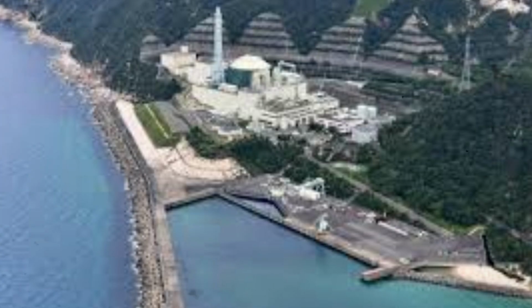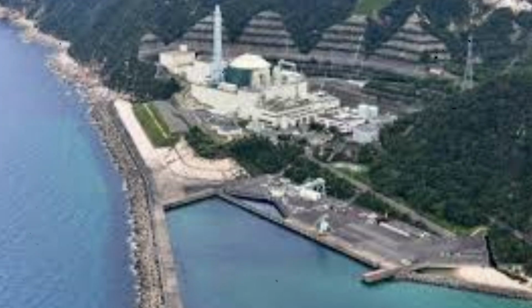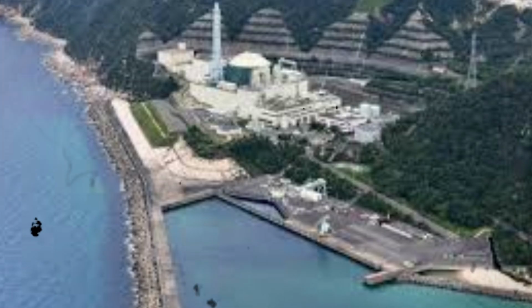However, initial notifications were based on preliminary assessments of leak severity that proved conservative as more information became available about the actual failure mechanism and consequences. Radiation monitoring throughout the facility confirmed that no radioactivity was released during the event. Secondary system sodium leaks pose no radiological hazard because secondary system sodium has no contact with reactor fuel or fission products. This confirmation was important for emergency response classification and public information activities.